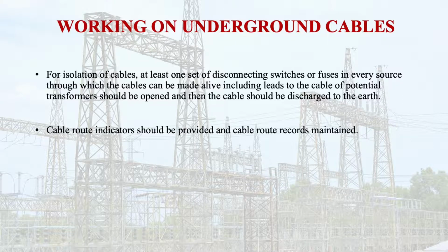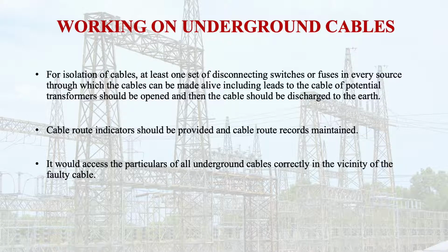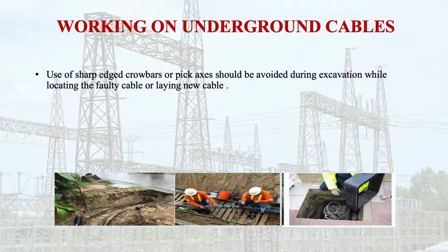Then the cable route indicators should be provided, and cable route records maintained, so that one can access the particulars of all underground cables correctly in the vicinity of the faulty cable. Use of sharp-edged crowbars or pickaxes should be avoided during the excavation while locating the faulty cable or laying a new cable. Otherwise the cable may be damaged, or there can be some hazard. All the cables in the vicinity in the fault area should be exposed and identified to establish the identification of the faulty cable.